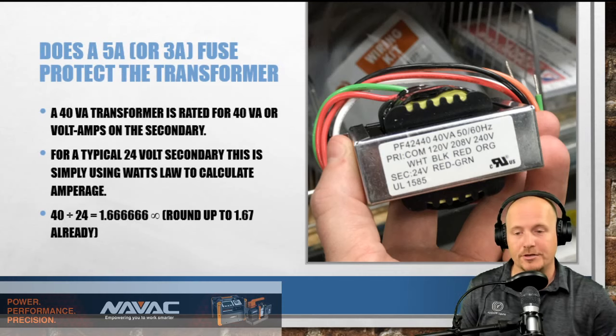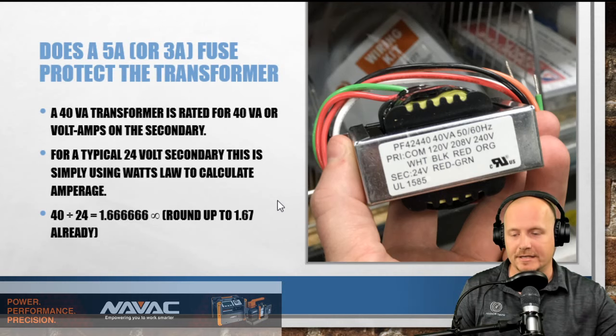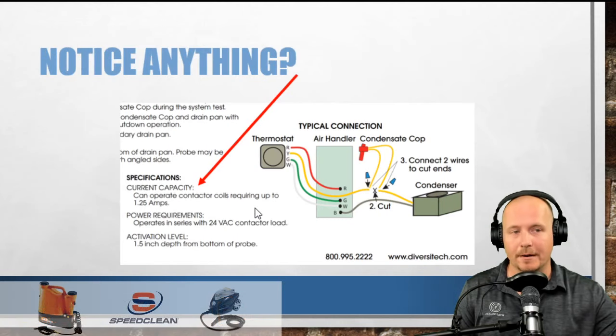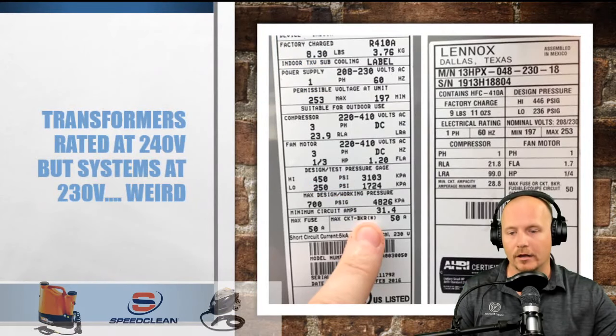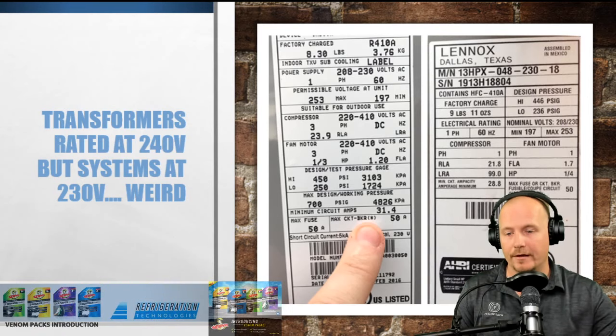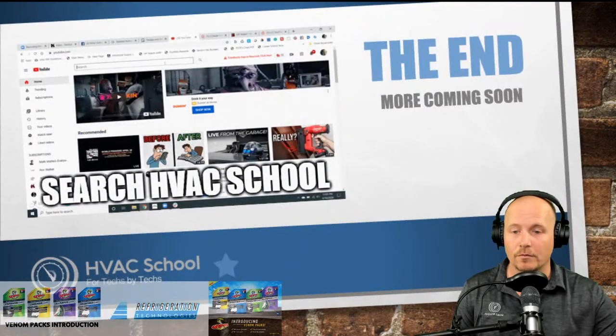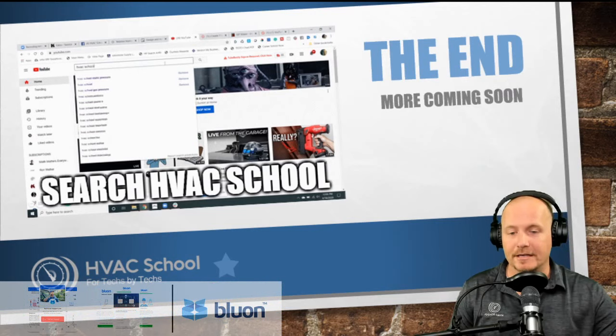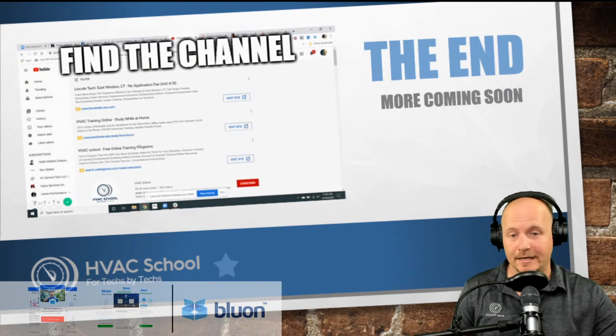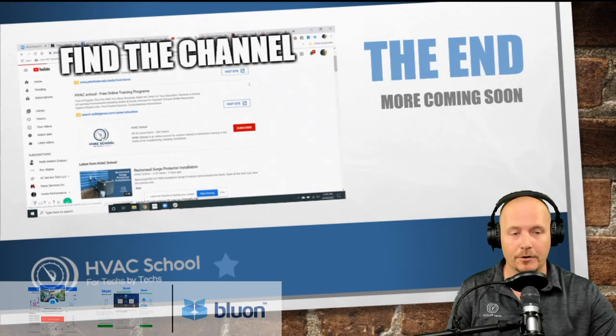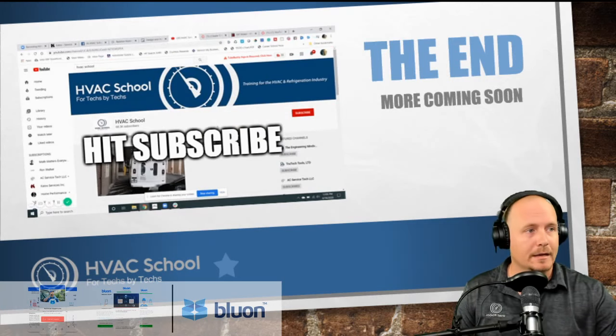I'm going to open up chat here, and you can tell me your opinions and thoughts on what we're covering in just a second. But those are my conclusions. I'm very interested in the current rating of the contacts on a lot of these float switches, because what I'm seeing is that they're generally well under the fuse rating of the circuit itself. That means you could potentially overload the contacts, resulting in a significant problem when those contacts fuse and the switch doesn't open up during a flood situation.